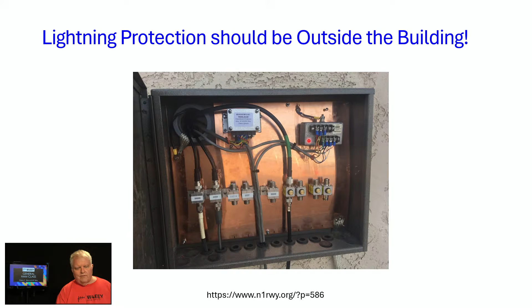Grounding wires and straps should be as short and direct as possible. Avoid right angle bends. All towers, masts, and antenna mounts should be grounded. And lightning grounds should be bonded to other safety grounds and earth connections when practical. Now, if it's out in the middle of your antenna field and you've got the house, it's not likely you're going to be able to interconnect those.